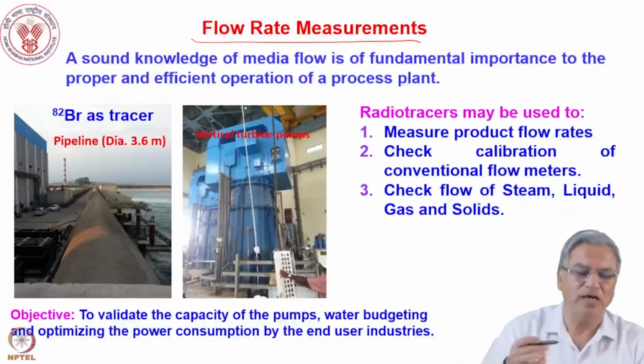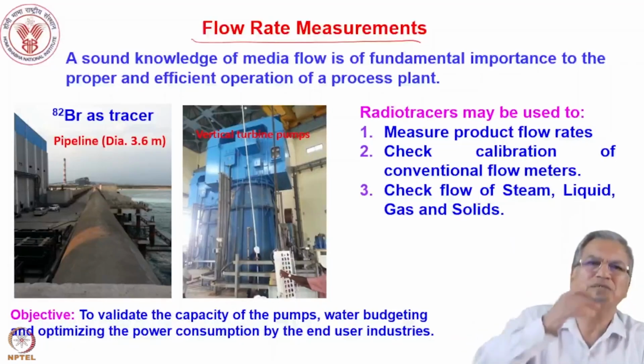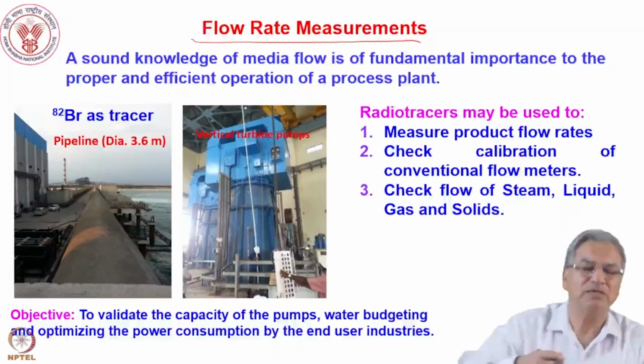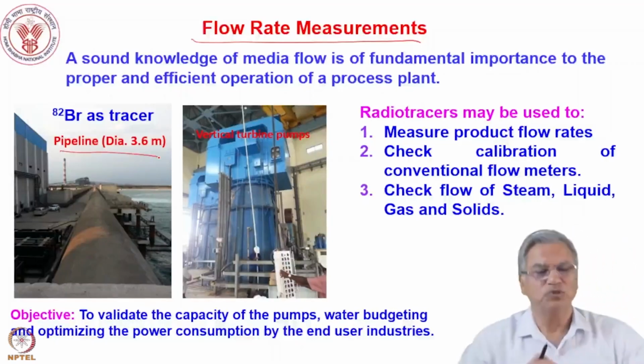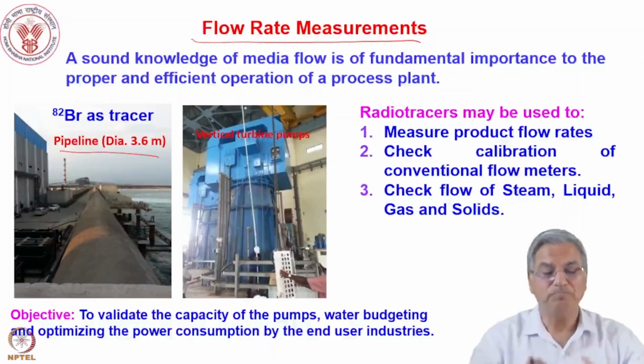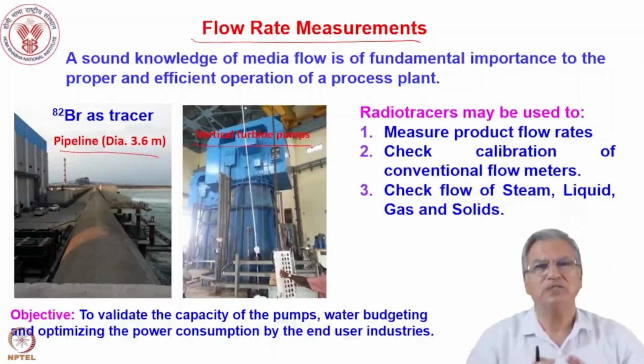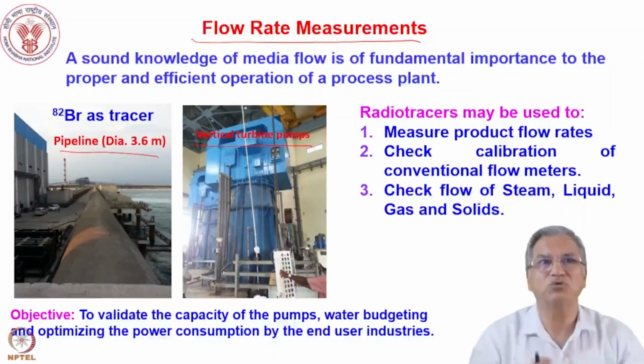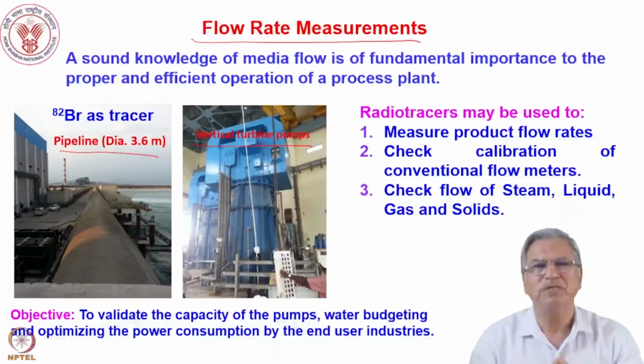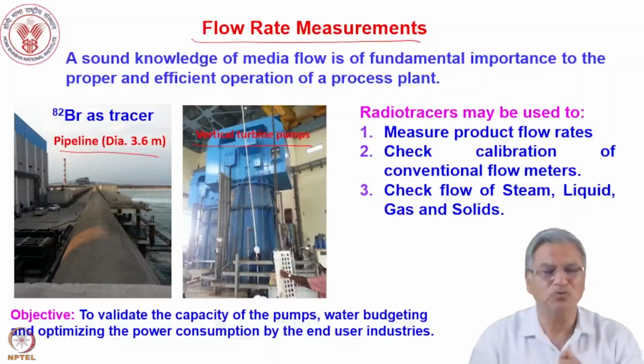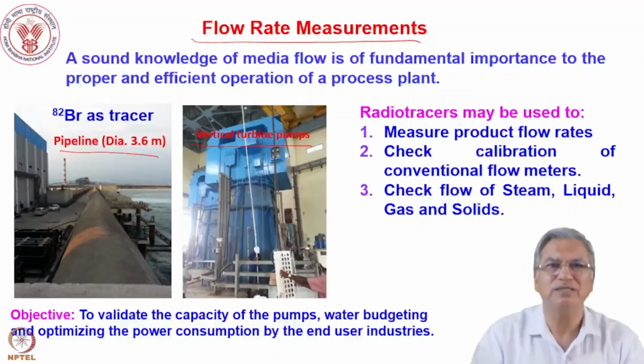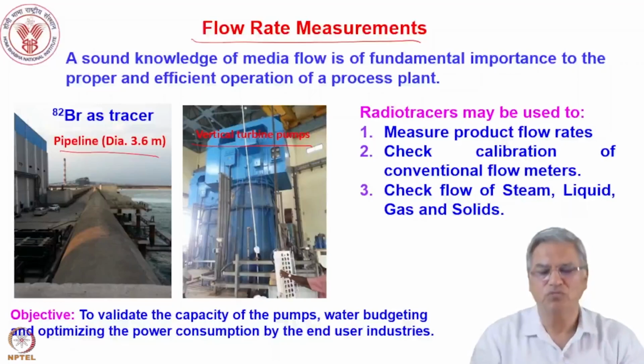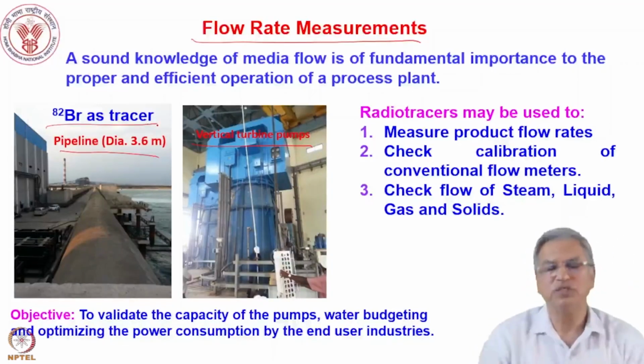For example, consider a hydroelectric plant with a 3.6-meter pipeline taking water to the turbine. The vertical turbine pumps have a rated capacity for how much water they will pump per minute, which is the capacity of the pump. You want to calibrate this because you need to know the power consumption and flow of the pump. To calibrate these pumps, you need to investigate the pump capacity and flow rate, and for this, bromine-82 can be used as a tracer.